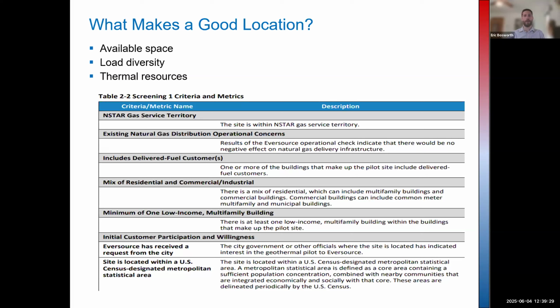The systems perform best if you have a more or less equal heating and cooling load. Unfortunately, there aren't many regions in the US where the heating and cooling load is balanced on its own - buildings tend to be one or the other. In your region, I believe you're a little heating dominated, but it's actually pretty close, which is good. You can use other thermal resources to balance the equation. In Framingham, we had an interesting situation where residential homes tended to be heating dominated on an annual basis, while commercial buildings tended to be cooling dominated. So those were the two levers we could pull - we looked at our loads and added or removed from one side or the other until we got to a point where we were net flat annually.